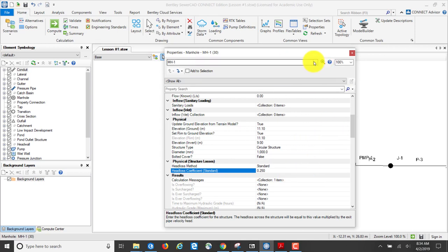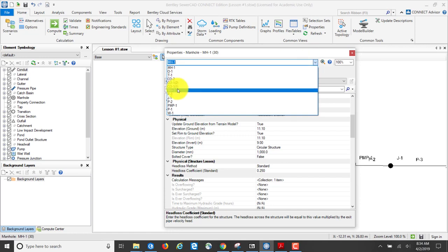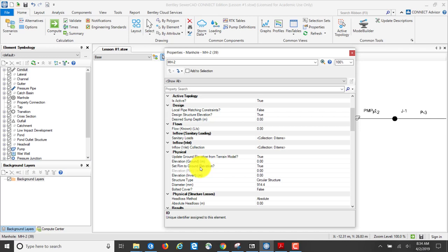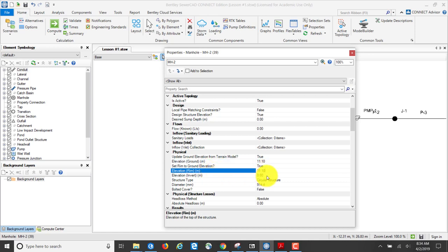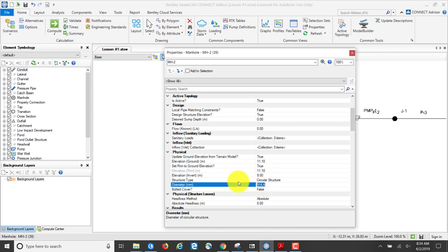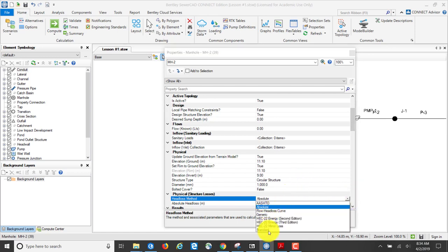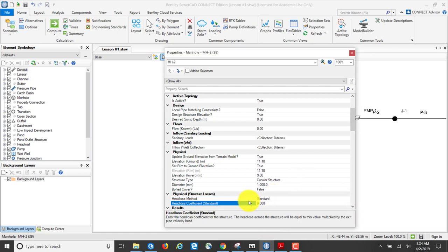Now I'm going to enter the same information for manhole number two: ground elevation 11.1, which sets the rim elevation automatically. Invert is 9, diameter 1000 millimeters, head loss method standard, and coefficient 0.25.